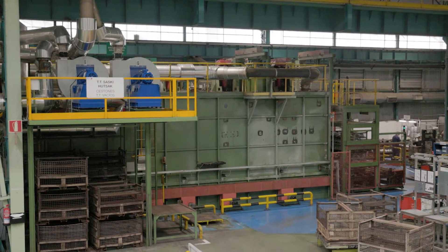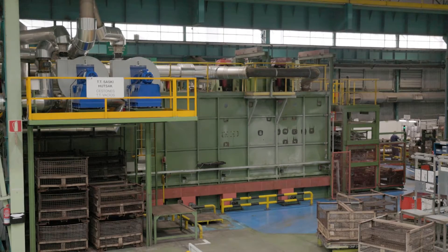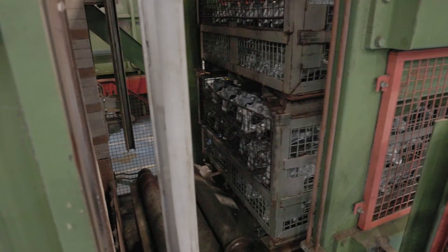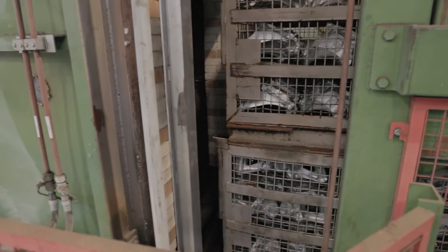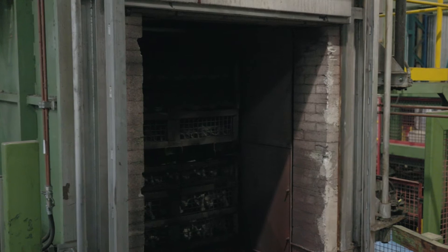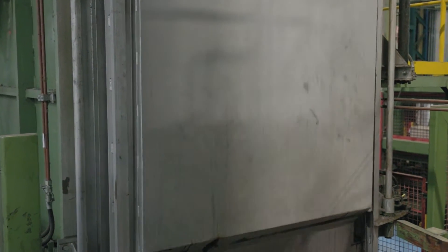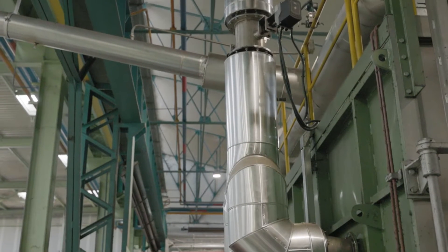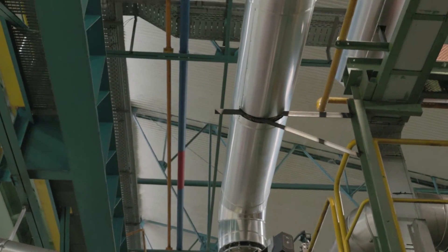One prototype of a heatpipe heat exchanger was installed at an aluminium alloy production plant of Fagor Ederlan in the Basque Country. The heat exchanger unit recovers waste heat from the furnace and channels it to an aging furnace where the aluminium parts are treated to improve some of their mechanical features. Because of space limitations within the production line, the heat exchanger unit was installed on top of one of its main furnaces.